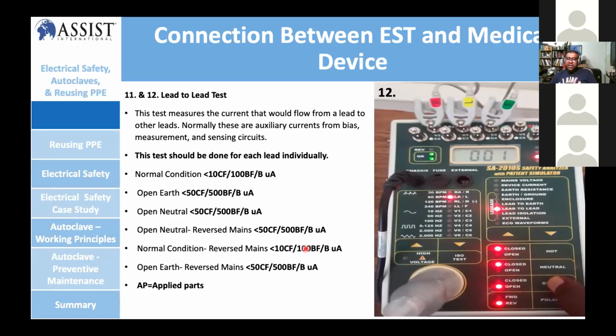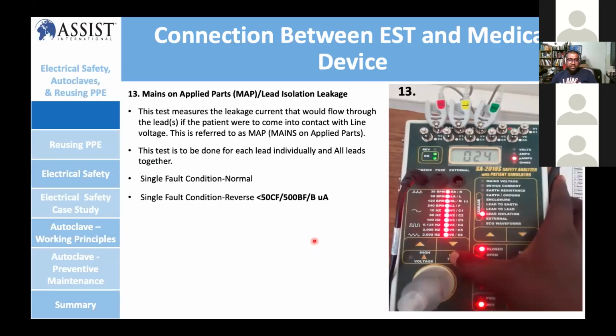So mains on applied parts, MAP, this is another measurement that you are testing between the leads as well, but you can do it individually or in groups. Normally, the best method is to do it on the group and see if the reading is above this particular range, and then try to do it one by one by changing the patient applied part setting. Normally what happens is one of the leads has contact with a live wire or something like that. You're going to see whether the remaining leads have some effect from that.